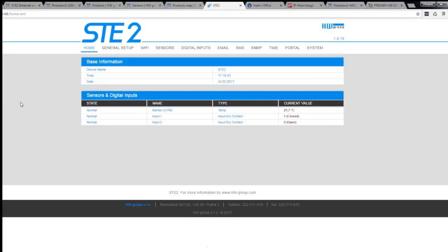So how do you interact with it? What does your dashboard look like? I'm going to share my screen and show you the STE2. We have three sensors hooked up to this right now — really one and two built in. We've got our temperature sensor, which is that wire you can see, and it's sitting right here. Looking at my screen, we have it up to 21.7 Celsius. The contact is set to closed right now — if I move it away, watch what happens with the screen. It goes to open, and I go back and it goes to closed.